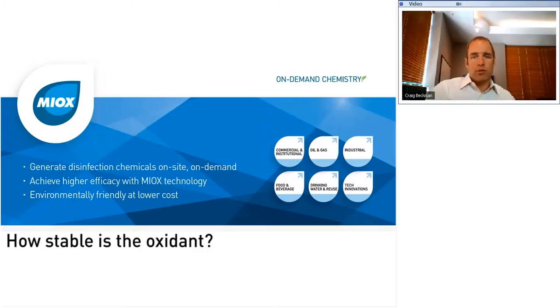Now, the mixed oxidant chemistry doesn't go back to water. You simply end up with sodium hypochlorite. So those other beneficial oxidants are the ones that are consumed, and you end up with a standard solution of sodium hypochlorite, but you don't get the benefit that maybe they were looking for with the mixed oxidant.